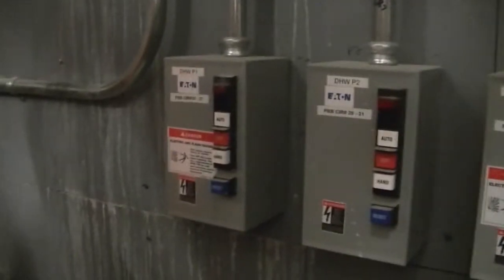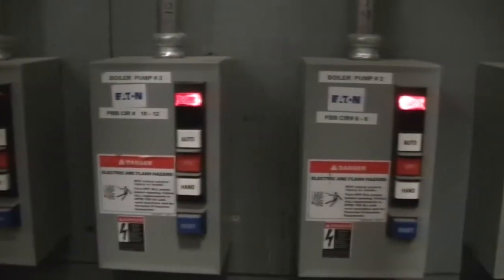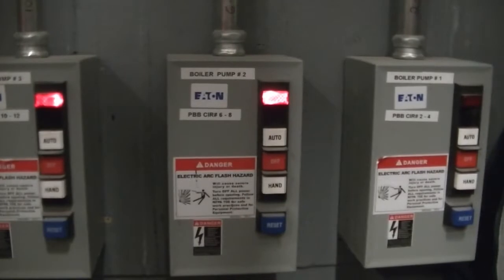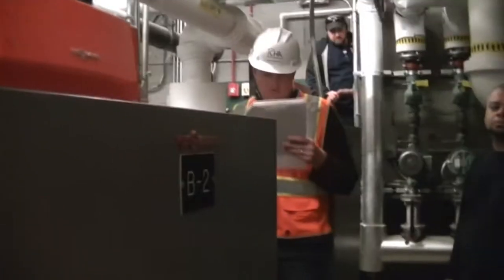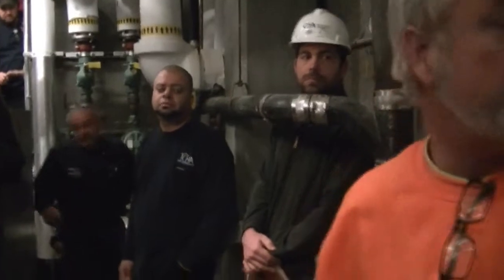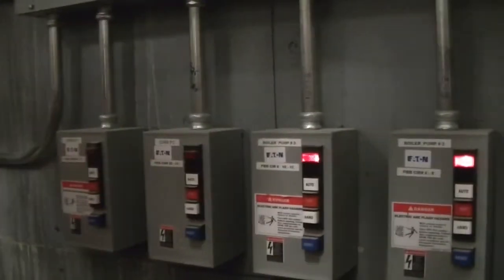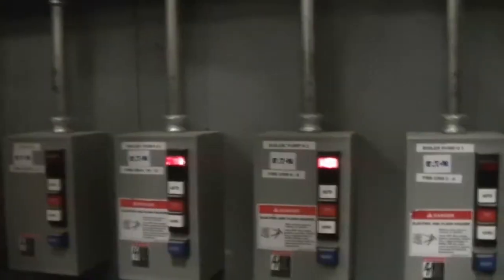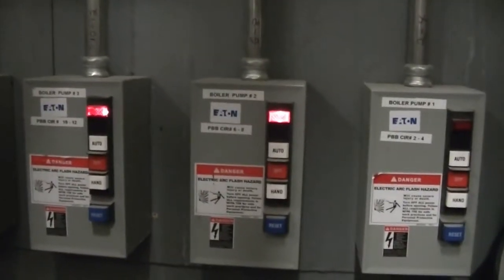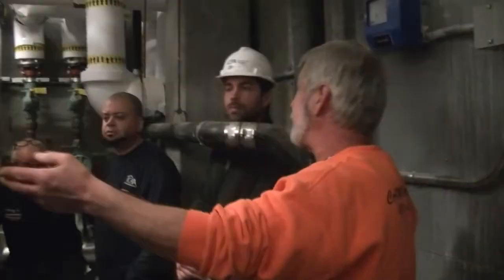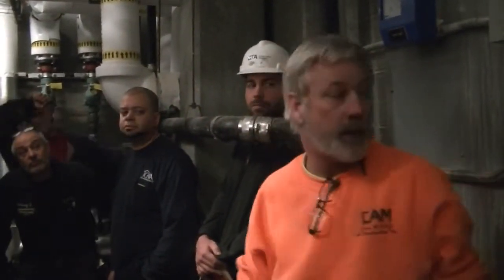The boiler tells its pump when to turn on. So in the back of the boiler, there's a pump relay box. That tells this pump to turn on. Right now, boiler number 3 and boiler number 2 are running and heating because the indicator light's on, okay? There are HOA switches on there. If you feel that the boiler's not turning the pump on, or the boiler's tripping out on high temperature because there's something wrong, usually you reset the starter, okay?